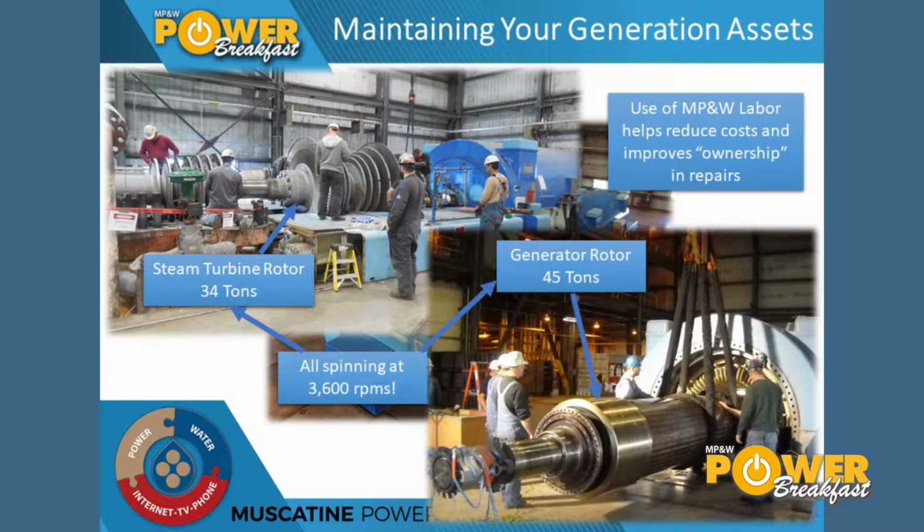I wanted to mention one of the big projects we have going on right now down at our generation facility: an overhaul of our Unit 9 turbine generator. This is a pretty major project that we do on a regular basis to ensure that the equipment continues to operate reliably. We have the turbine rotor right here. It's about a 34-ton piece of equipment that drives the generator rotor here that you can see being pulled out. It's about 45 tons, or about 90,000 pounds. And all of these systems operate at 3,600 RPMs, or spinning 60 times per second. So a significant amount of weight. And the tolerances on some of this turbine equipment are as small as 20 thousandths of an inch. So that much mass operating at those tolerances, as Sal mentioned, is a pretty complex system that we operate here.